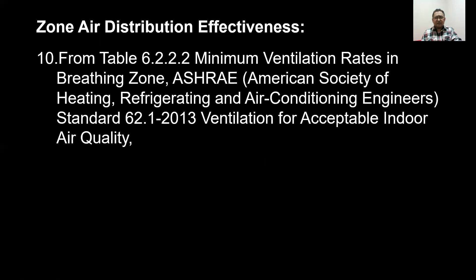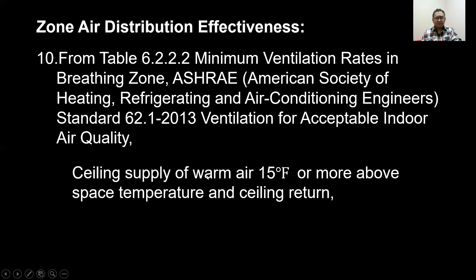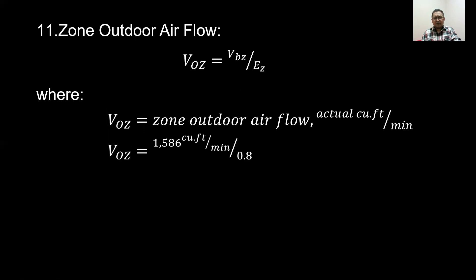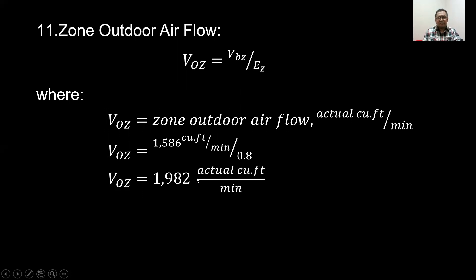For air distribution effectiveness, from table 6.2.2.2 of ASHRAE standard 62.1-2013, for ceiling supply of warm air 15°F or more above space temperature and ceiling return, the effectiveness factor is 0.8. So we divide the outdoor airflow of 1,586 CFM by 0.8, giving us 1,982 actual cubic feet per minute.